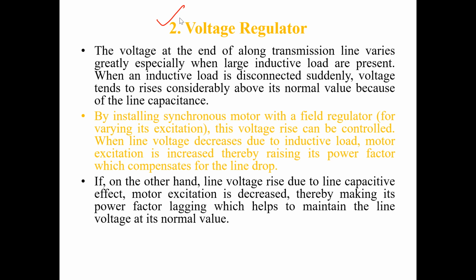So one of the voltage improvement techniques is by using this synchronous motor. The voltage at the end of a long transmission line varies greatly, especially when large inductive loads are present. When the inductive load is suddenly disconnected, voltage tends to rise considerably above its normal value because of line capacitance. By inserting a synchronous motor with a field regulator, this voltage rise can be controlled.